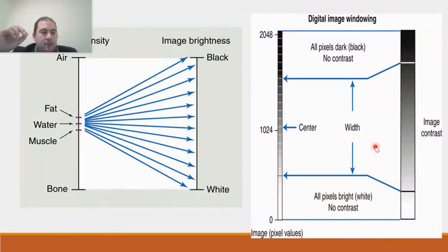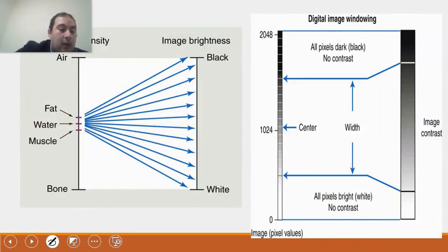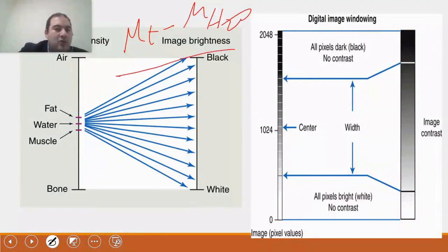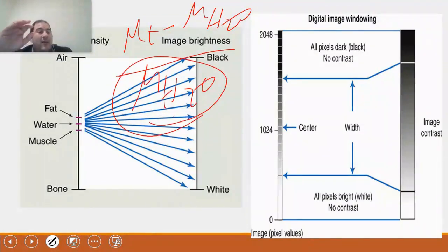If we observe, for example, the CT number, the standard CT number refers to what? It refers to the attenuation of the tissue, meaning the attenuation of bone, soft tissue, or fat compared to the attenuation of water. This means that water serves as the standard value. Therefore, water phantom calibration is performed to ensure that the CT number of water is 0 plus or minus 5.